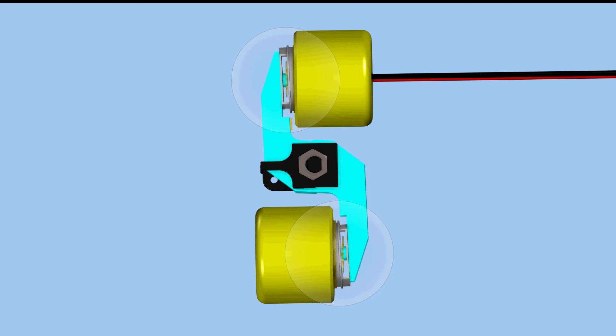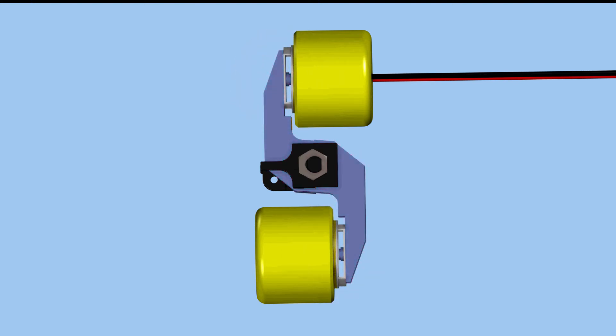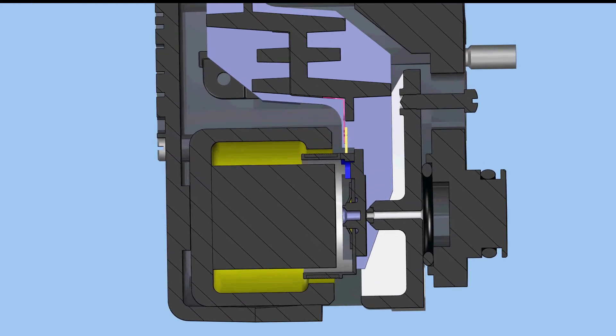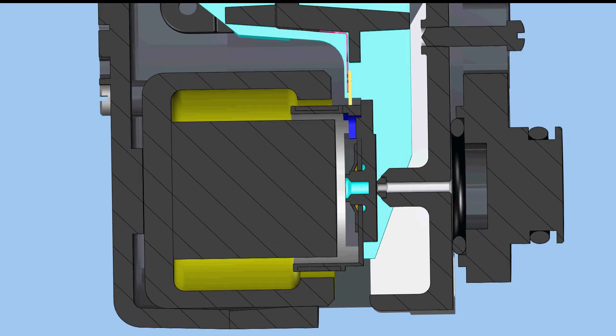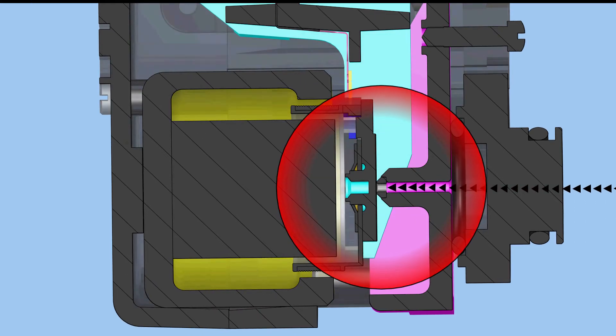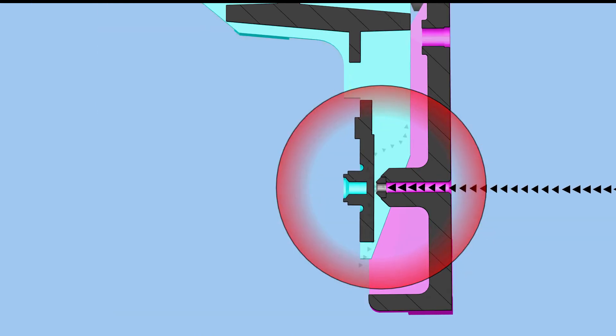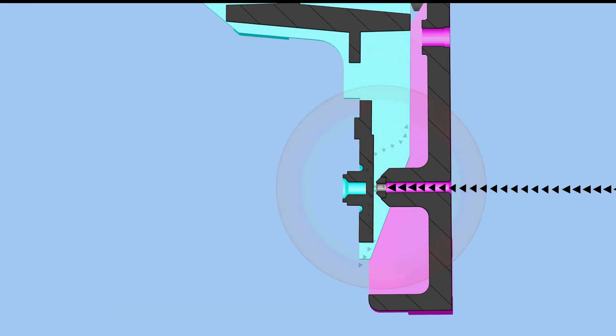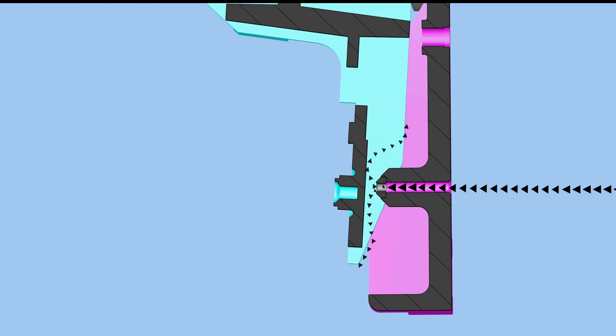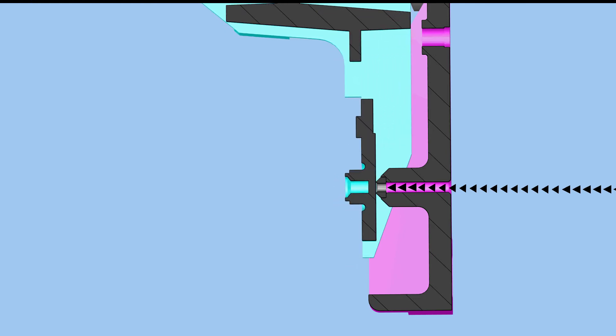This change in magnetism affects the position of a beam. If magnetism is increased, the beam moves toward the magnet, and as magnetism is decreased, it moves away. On the opposite end of the beam is a nozzle and flapper assembly. The movement of the beam positions the flapper in relationship to the nozzle to create changes in nozzle pressure.